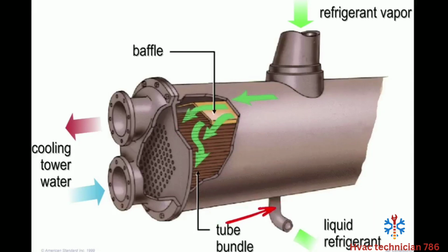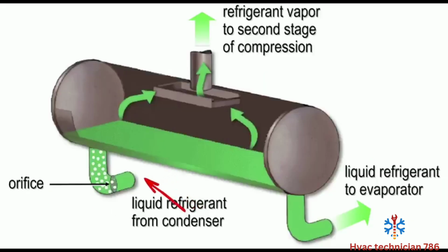There will be a saturation sensor in the liquid line. That is how the chiller is able to determine its saturation temperature, because this refrigerant leaving is going to be at a saturated temp. That liquid line from the condenser flows into this first stage orifice plate. We will flow through this orifice plate. This is just a fixed bore metering device. That's all you have to think of it. It's just a plate with a whole bunch of holes in it.